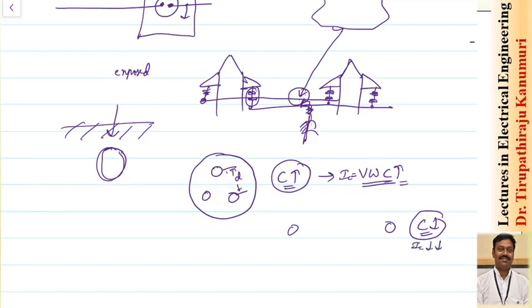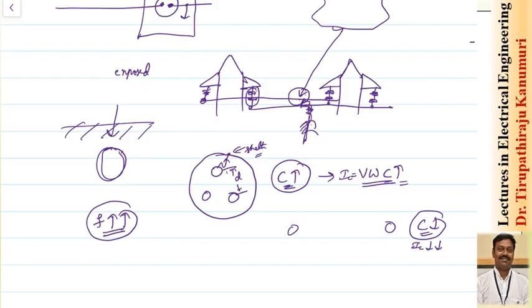In overhead transmission lines, because the conductor spacing is very high, the capacitance is less and the charging current is less. However, having more capacitance is advantageous for switching transients and lightning surges. Since the frequency of these transients is very high and a capacitor acts as a short circuit for high frequency, it bypasses lightning surge currents to the sheath — same for switching transients.